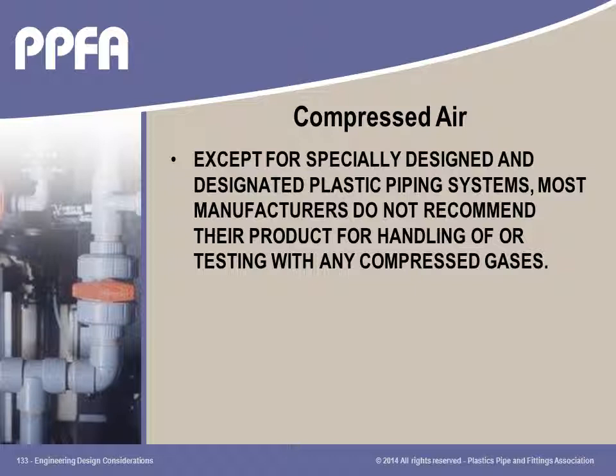Do not use any thermoplastic piping in transporting of or in testing with compressed air or gases. The one exception is the use of polyethylene gas piping and other specially formulated plastic compounds specifically designed to handle compressed gases. Always follow the manufacturer's instructions.